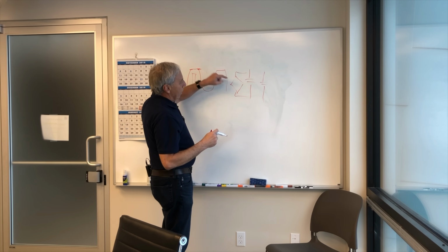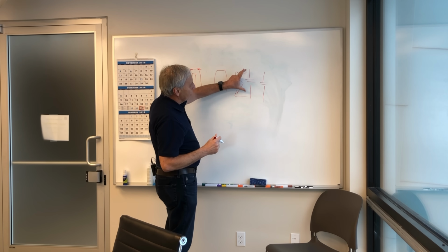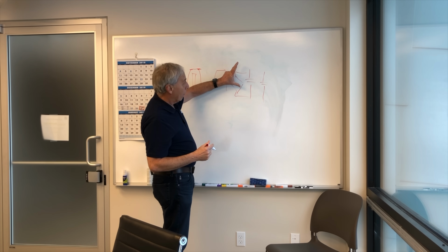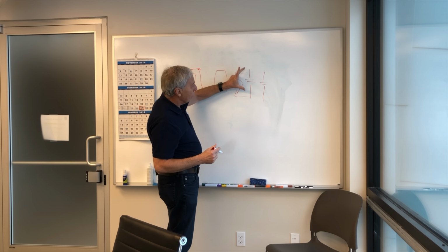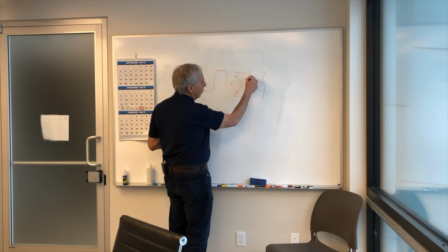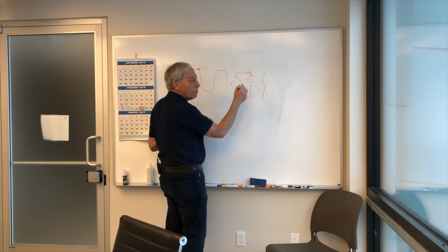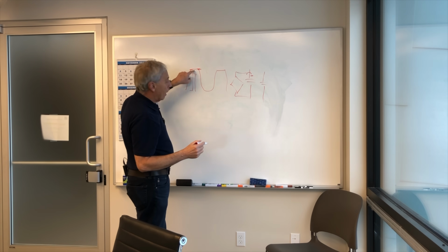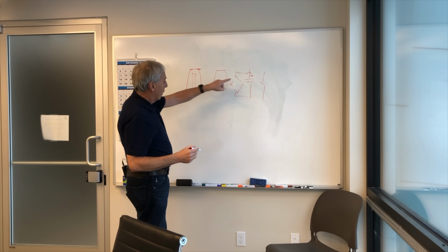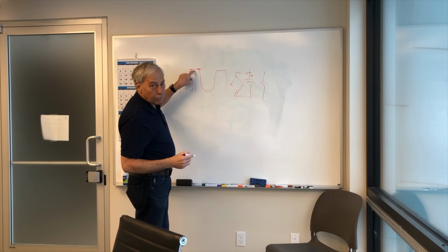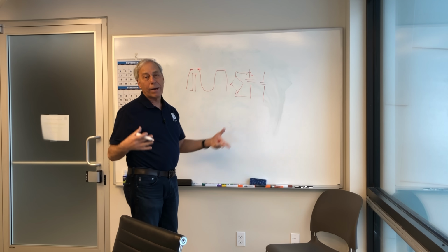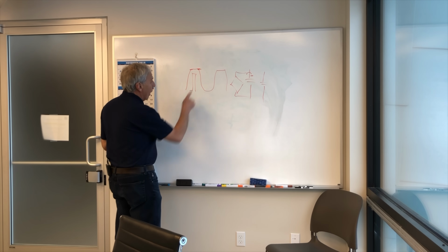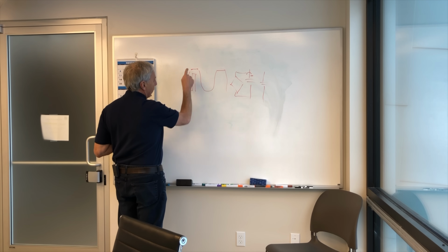And every time the capacitors drain a little bit, they're like batteries, they kind of hold on. So between cycles, they'll drain, but they don't drain all the way. So when it comes back for another cycle, their voltage is down to here. We just have to top off their supply. That's what's happening. And this top off of the supply, because of these capacitors, is what's drawing all the current to just get them back up, okay? And that causes a flat top waveform over here.